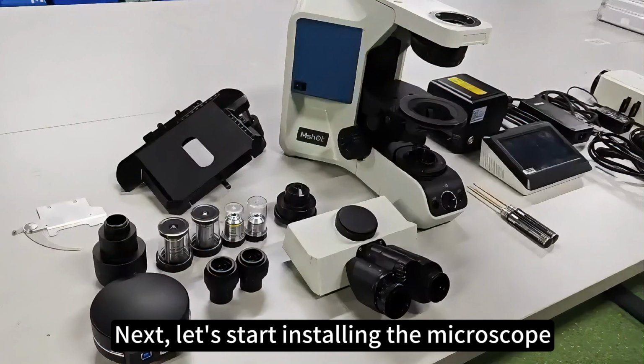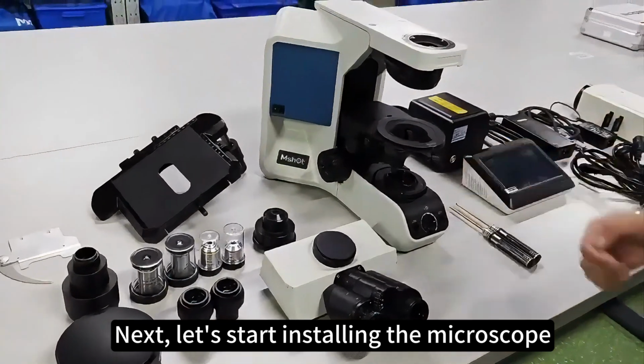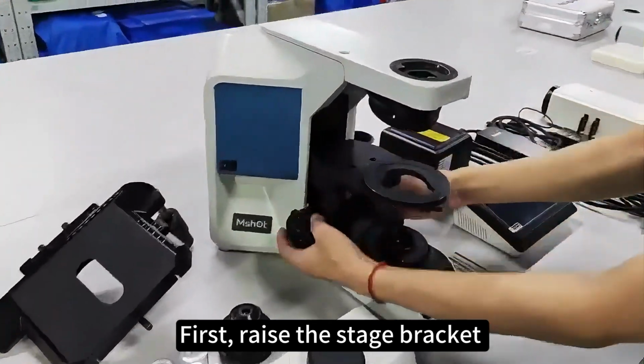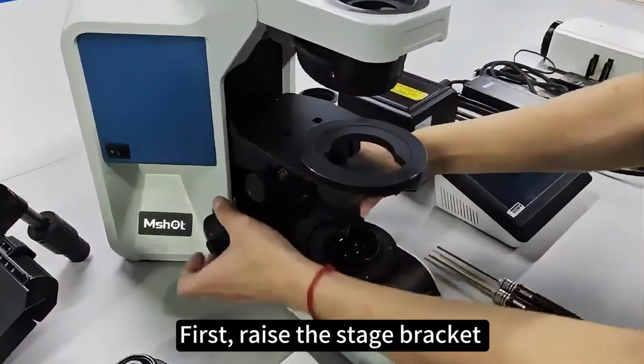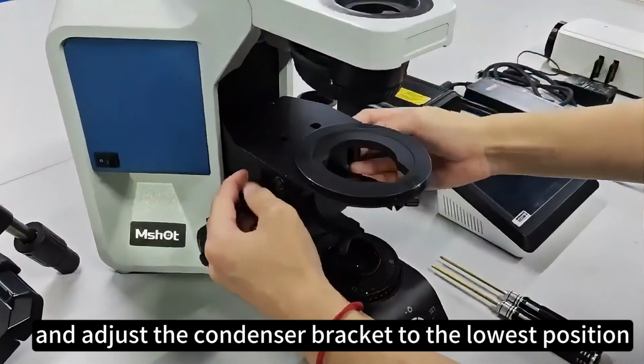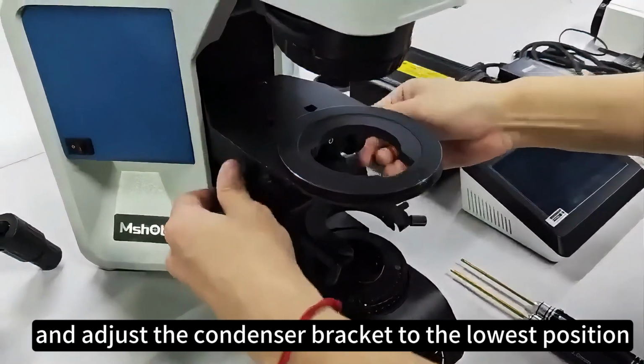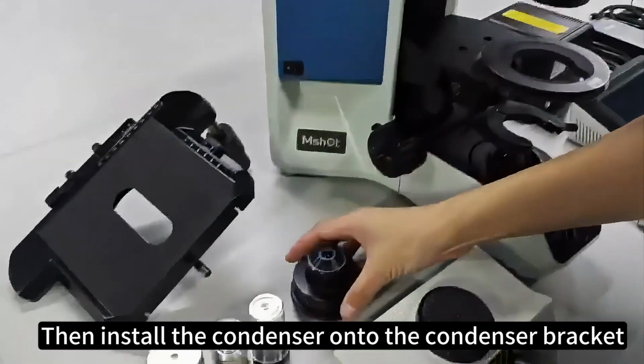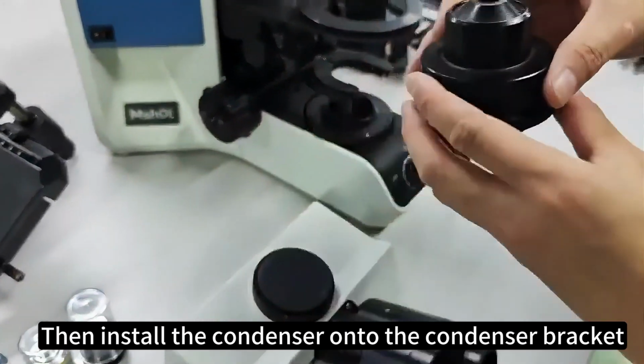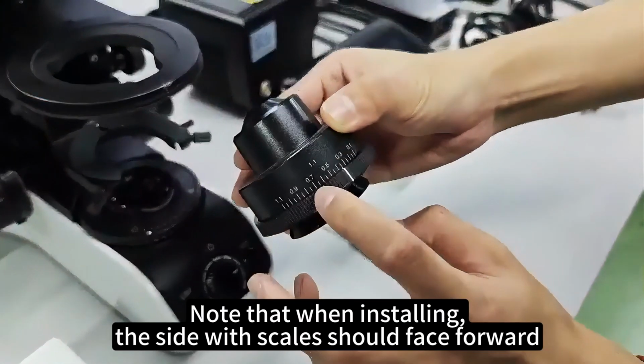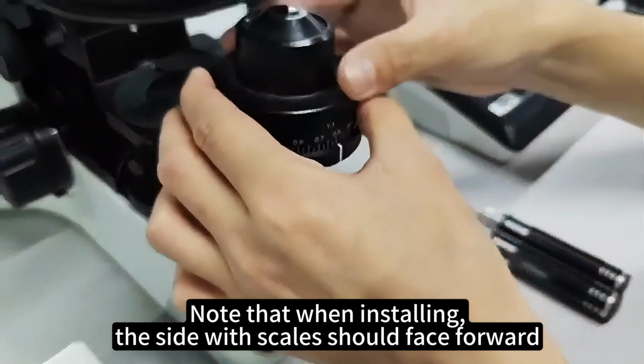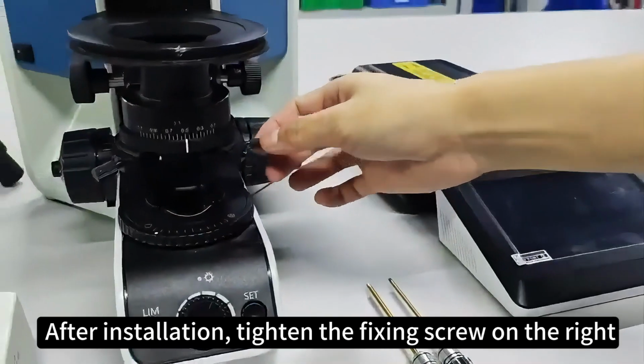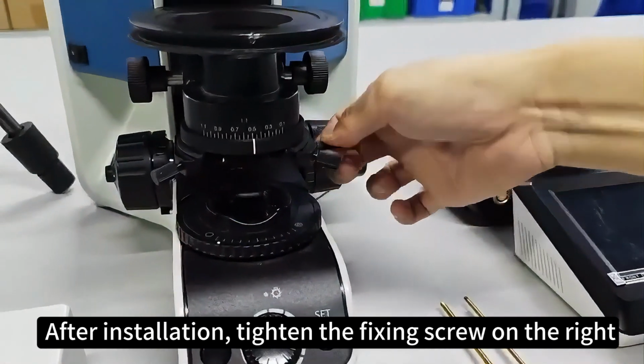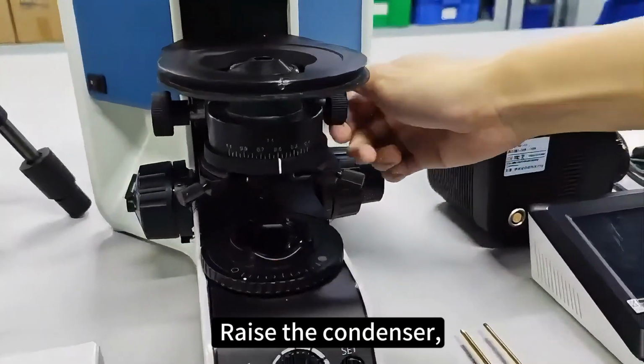Next, let's start installing the microscope. First, raise the stage bracket and adjust the condenser bracket to the lowest position. Then install the condenser onto the condenser bracket. Note that when installing, the side with scales should face forward. After installation, tighten the fixing screw on the right. Raise the condenser.